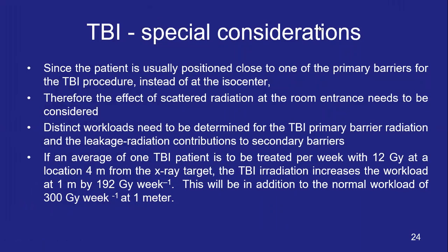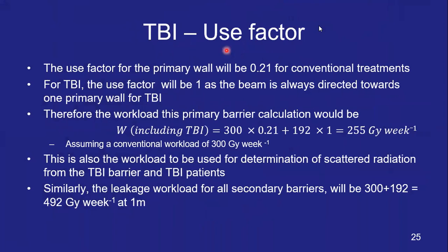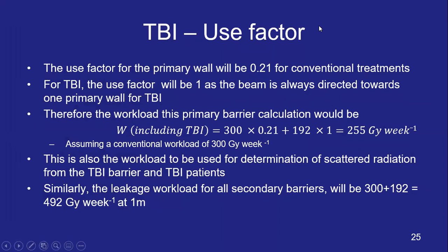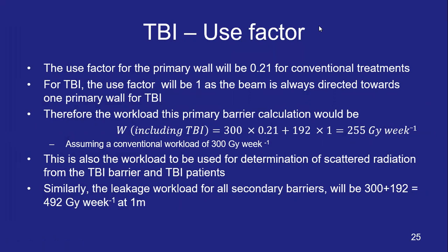The use factor for a primary wall in conventional treatment is 0.21, but for TBI the use factor is 1, as the beam is always directed toward one primary wall. The combined workload for the primary barrier is: conventional workload 300 × use factor 0.21, plus TBI workload 192 × use factor 1, totaling 255 gray per week. This is also the workload used for scattered radiation from the TBI barrier and TBI patients. For leakage radiation, all secondary barriers use the total workload of 300 + 192 = 492 gray per week at one meter.